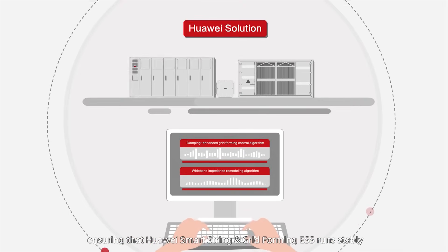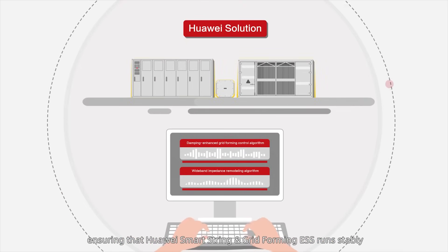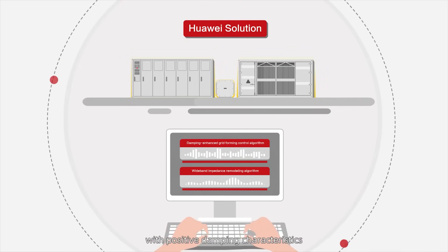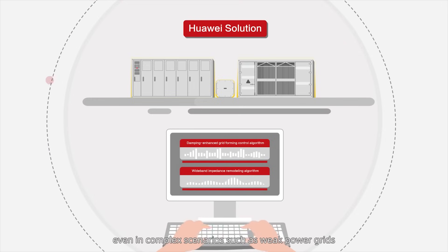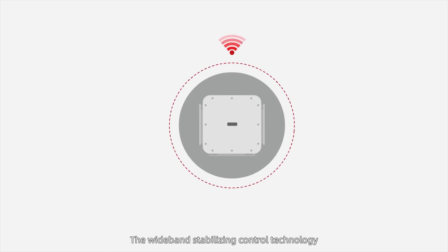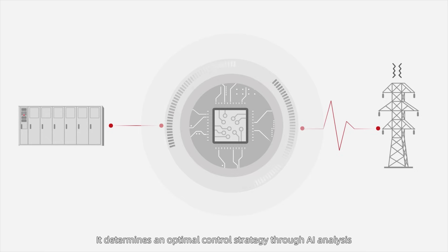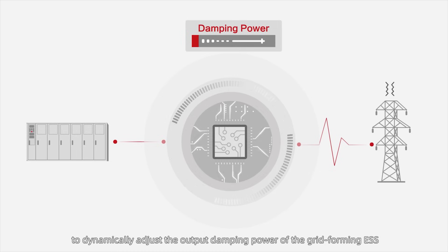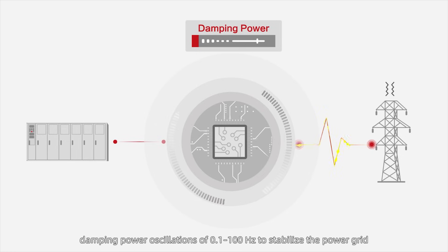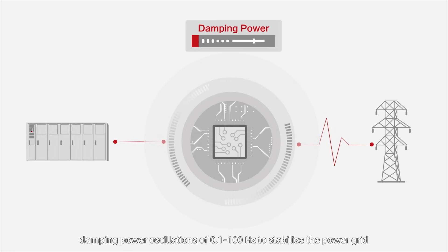This ensures that Huawei SmartString and Gridforming ESS run stably with positive damping characteristics, even in complex scenarios such as weak power grids. The wideband stabilizing control technology proactively detects power grid oscillation signals, determines an optimal control strategy through AI analysis to dynamically adjust the output damping power of the grid-forming ESS, damping power oscillations of 0.1 to 100 Hz to stabilize the power grid.